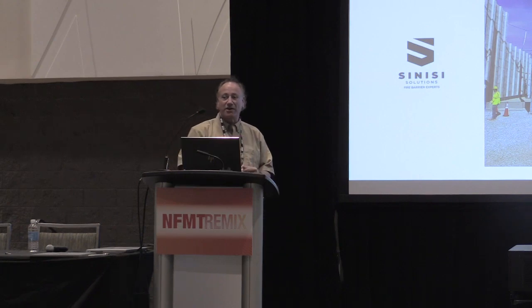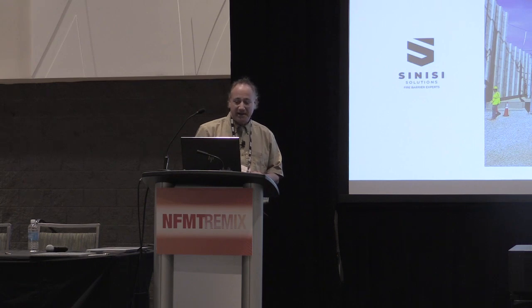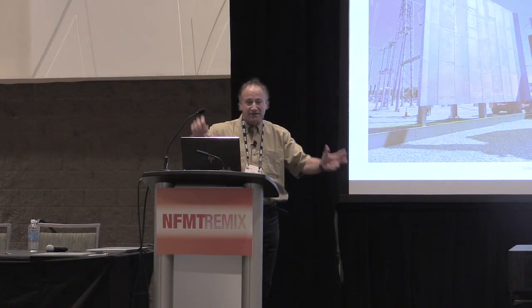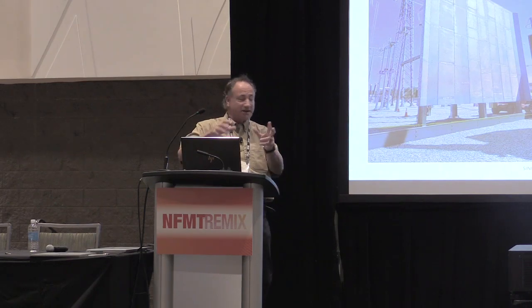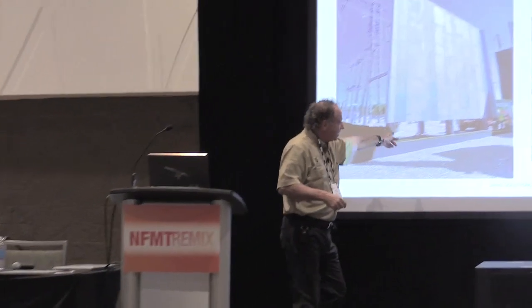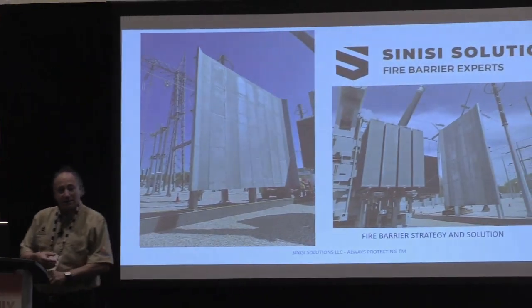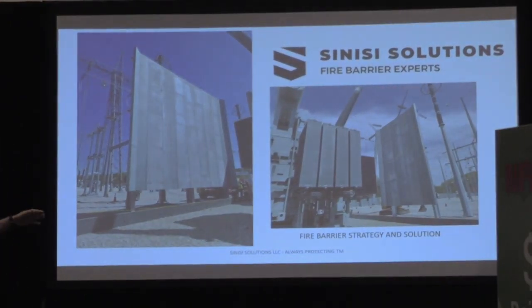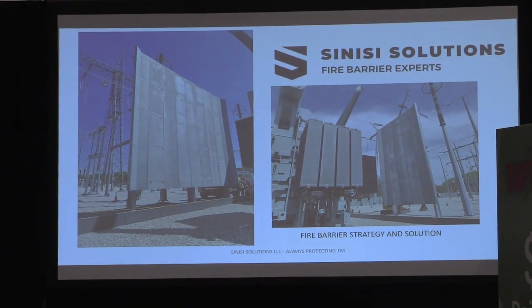These are really critical infrastructure protection systems. You just don't put them up indiscriminately. They're not noise barriers that you see along the parkway - they're fire rated, explosion rated. Typical strategic fire barriers are located in places that protect line of sight, protect people, protect the equipment.